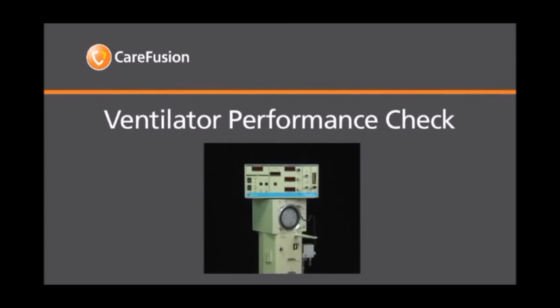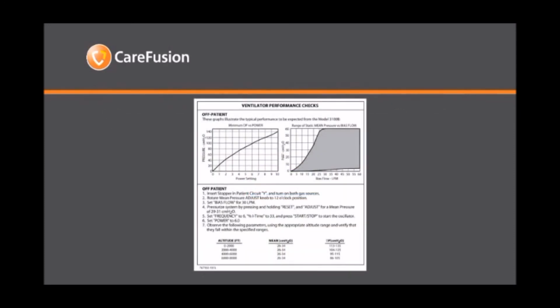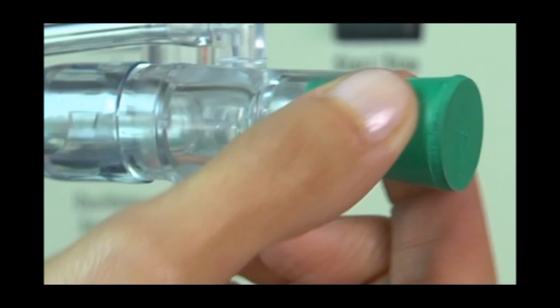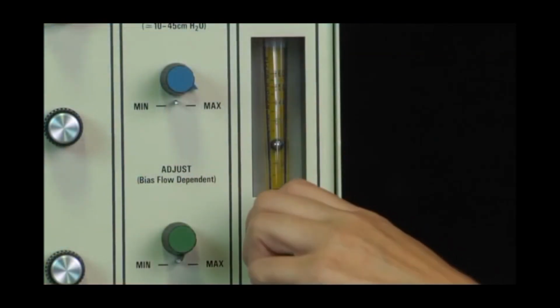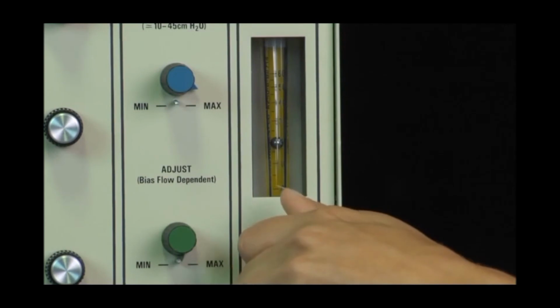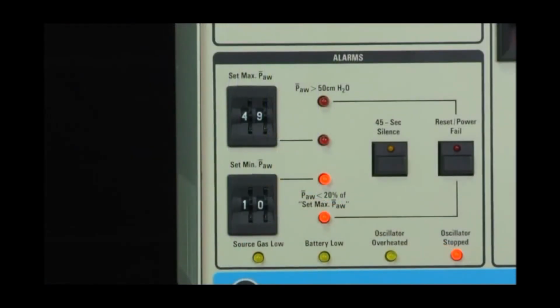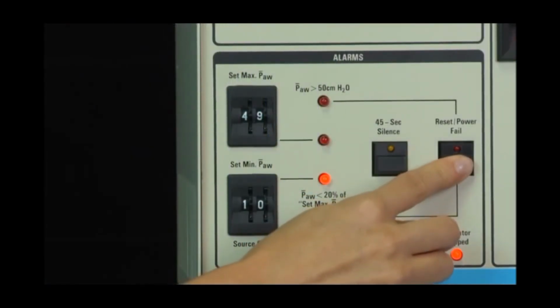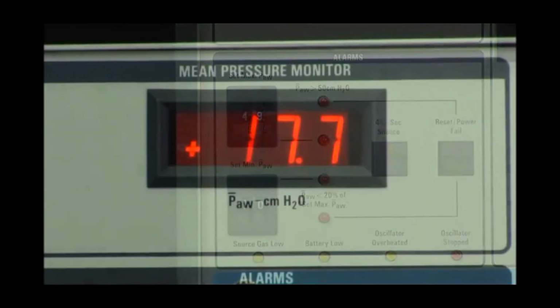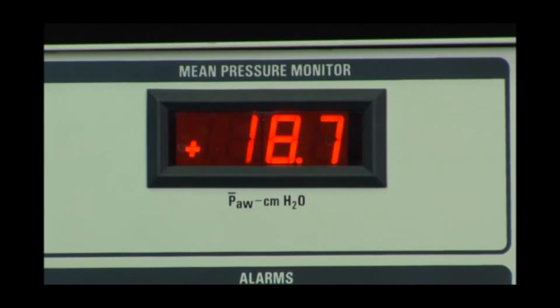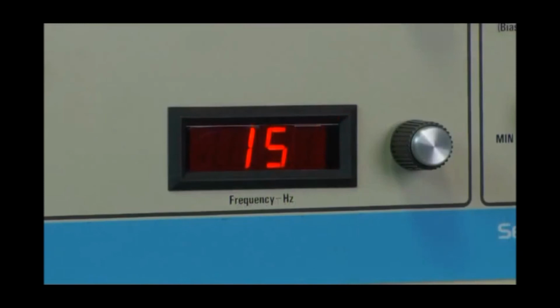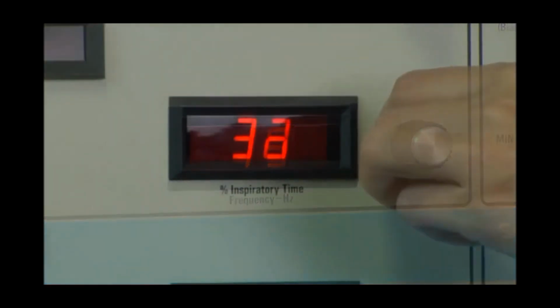Ventilator performance check. To carry out the ventilator performance check, follow the instructions on the label located on the top of the ventilator. Insert the stopper into the circuit at the patient Y. Set the bias flow to 20 liters per minute. Press and hold the reset button to allow the patient circuit to pressurize. Set the mean airway pressure to 19 to 21 centimeters of water pressure. Set the frequency to 15 and the inspiratory time to 33.